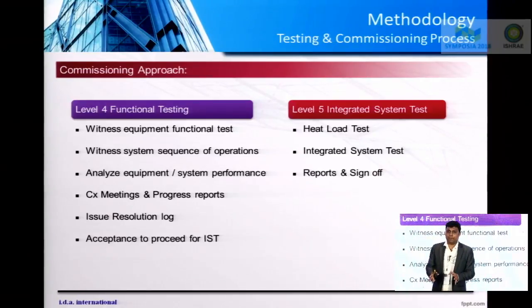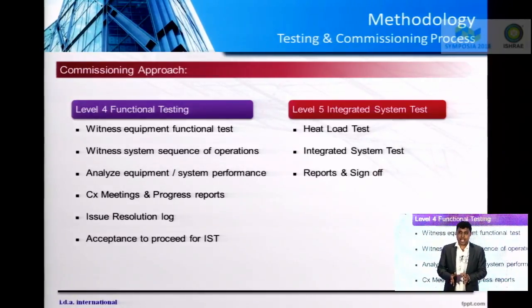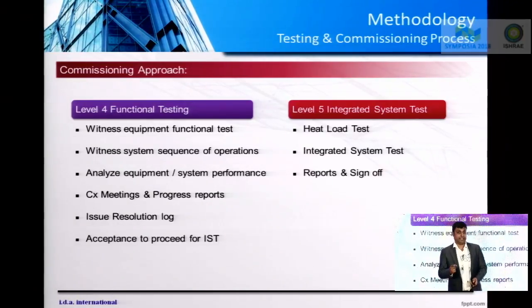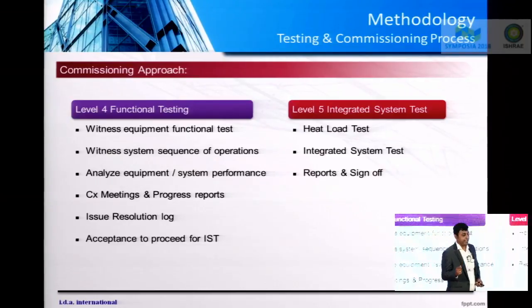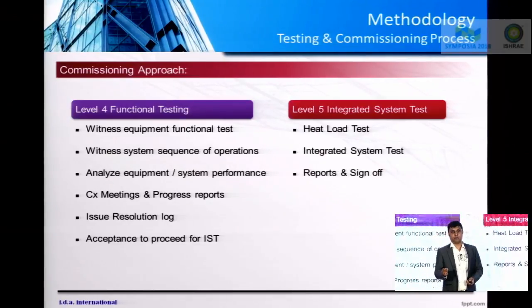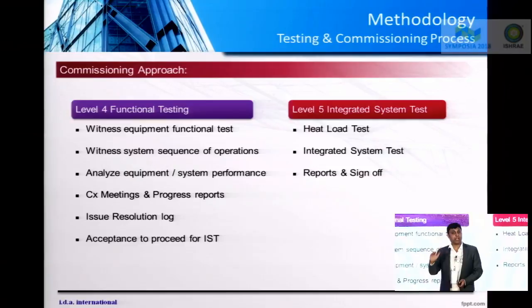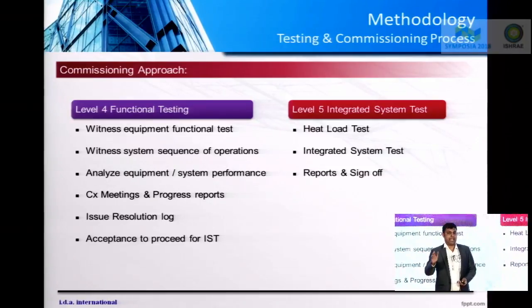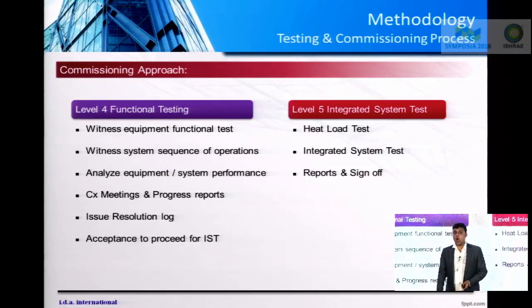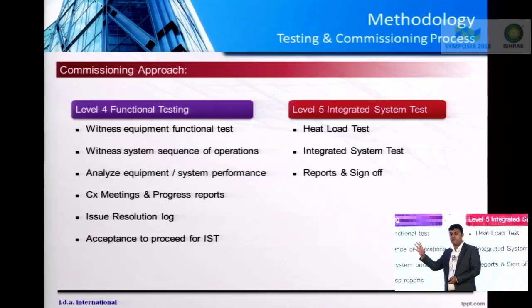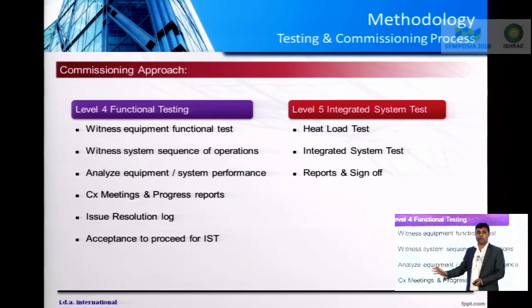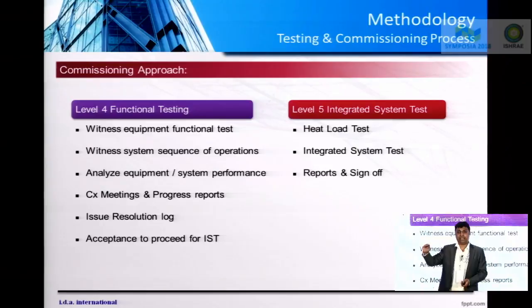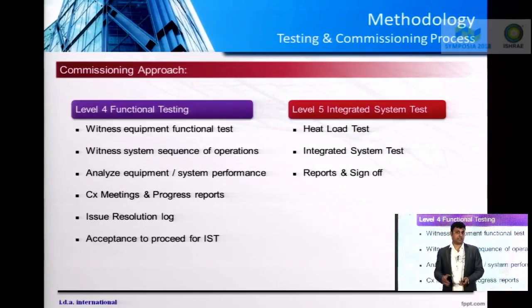The moment you complete your level 4, you will jump to level 5, which is the integrated system test for a data center, which is the very critical and the most important step of commissioning for a data center. Now, you cannot jump to level 5 integrated system test unless all the issues that you have identified during level 2 to level 4 are mitigated. It's a prerequisite, a pre-test condition.